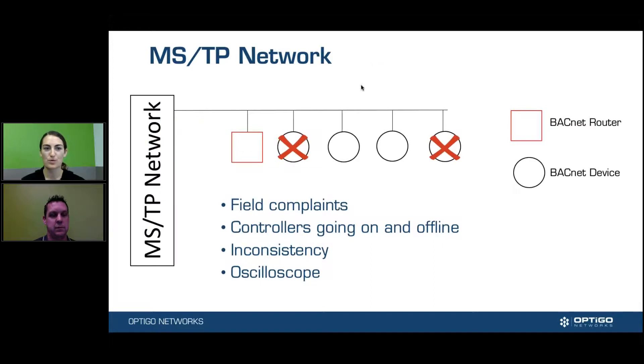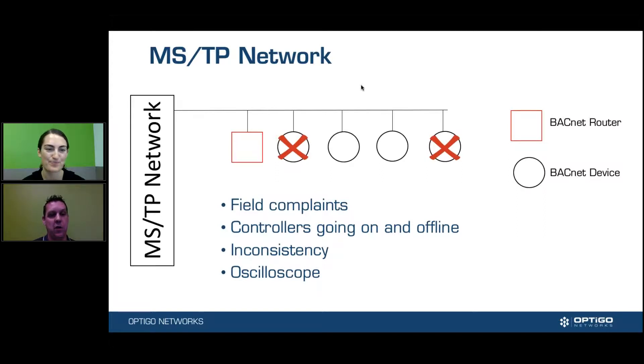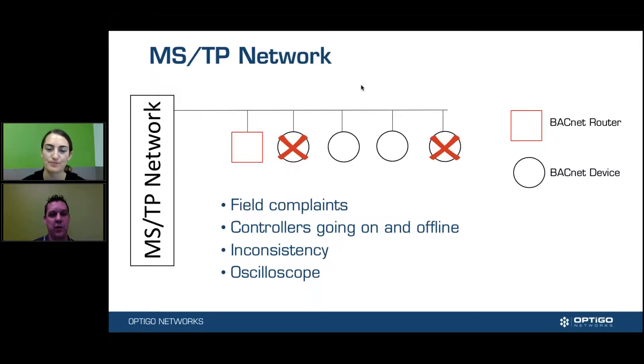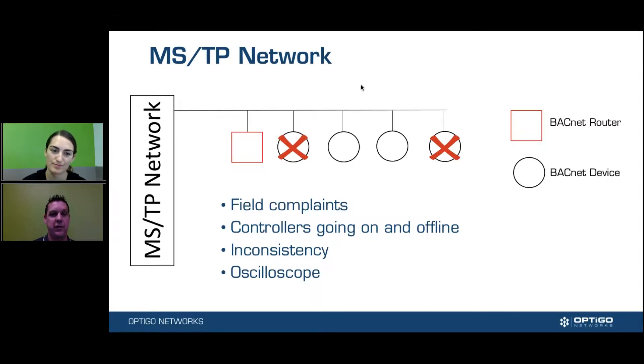So what do you do about it? The biggest thing is you've got to find it — figure out where your problem is. Normally, field complaints on an up-and-running system or an occupied building are the easiest source. Someone's going to say they're cold because the box isn't online and they're not getting the data. Also, controllers will go online and offline, especially during your commissioning period, and it's just random and you can't quite figure it out. It seems like the device is offline, but when you click on it in your server, it disappears from you.